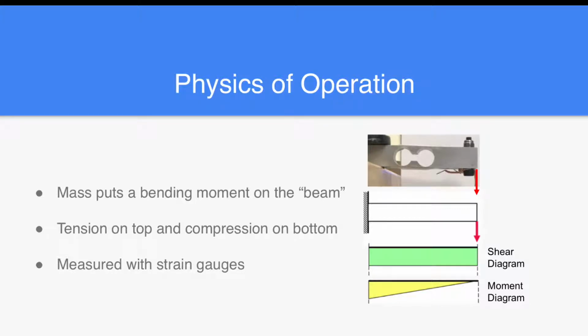The load cell works on the principles of a cantilevered beam. When a mass is placed on the end, a bending moment is put on the beam. This causes tension on the top and compression on the bottom. With a strain gauge mounted on top and bottom, a change in resistance occurs and a voltage output is given.